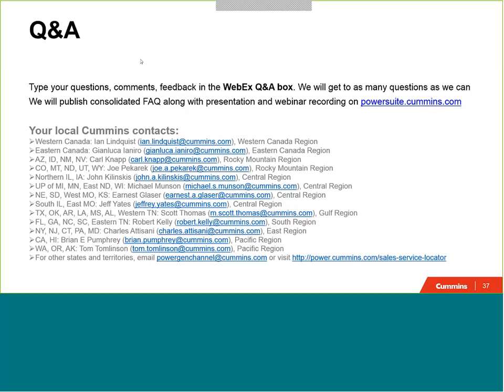All right, next question. Will you recommend to wire a genset, ATS, and switchgear together during the factory acceptance test? Yes, factory acceptance. So the question is about installing or testing the entire power system within the manufacturer's facility as part of the factory acceptance test. For the most part, many generator set manufacturers may not be able to accommodate a full system setup within their facility. The other thing to consider is that most generator set manufacturers are not the manufacturers of their own lines of transfer switches and switchgear, so you may run into some issues there as well. So I'd say typically we do not see this sort of testing done.